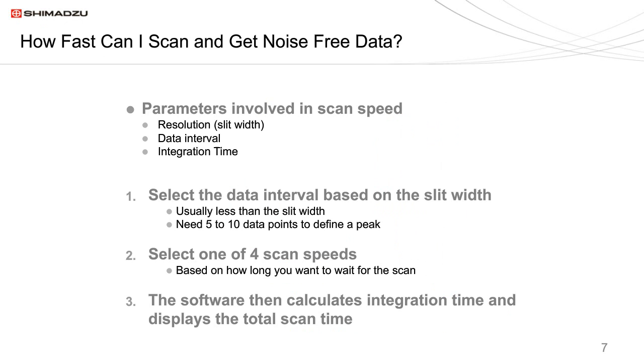In most modern instruments, you don't enter the scan speed directly — it is usually derived from the slit width, the data interval, and the integration time. Many competitors allow you to enter all three of these, which leads to a lot of trial and error and noisy spectra. Shimadzu has a better plan: first you select the slit width, then agree on a data interval — usually less than the slit width, with five to ten data points needed to define the peak. After that, you select one of four scan speeds: fast, medium, slow, or very slow. The software then calculates an appropriate integration time and displays the total scan time.